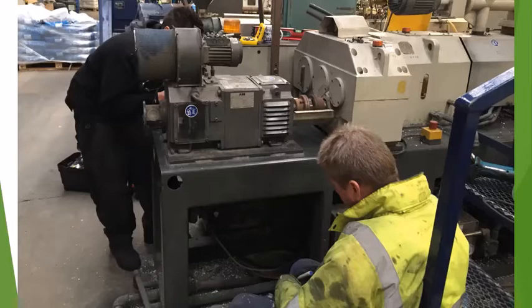Like Barnaby was saying, some extruders, when you're running PVC, have such extreme torque requirements compared to poly film. Those almost run like water once you start getting them warmed up. But some of that PVC is really, really tough stuff in that extruder barrel. And so you've got to make sure that the motor is going to produce the torque necessary.